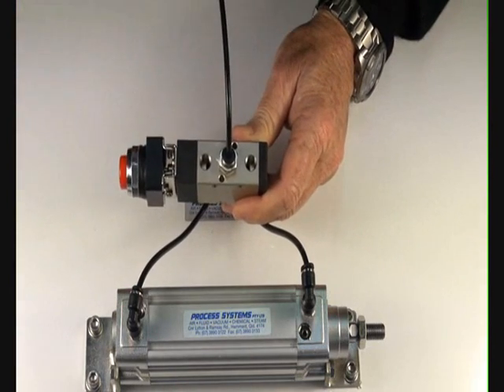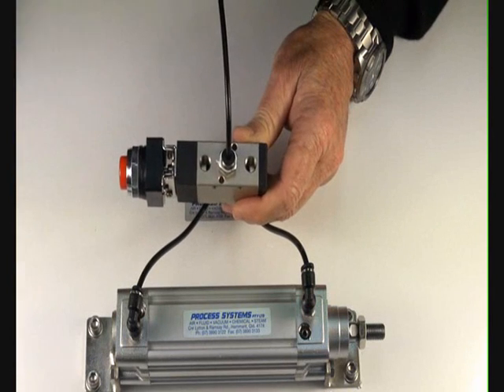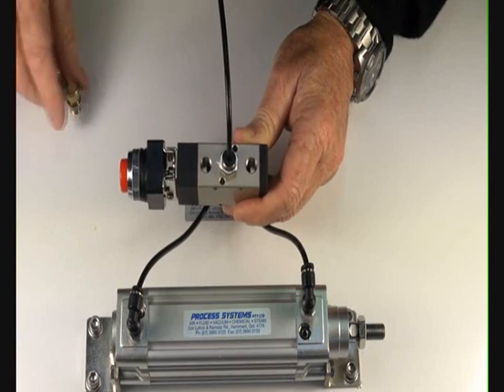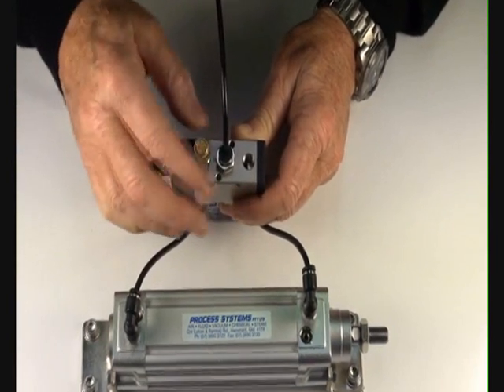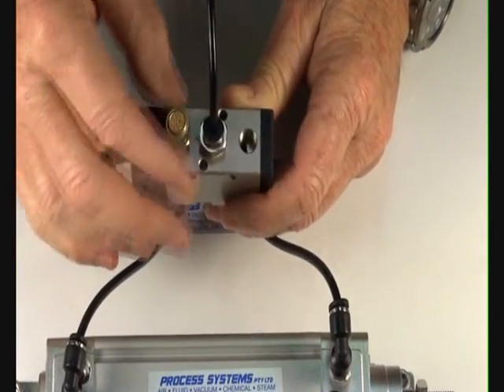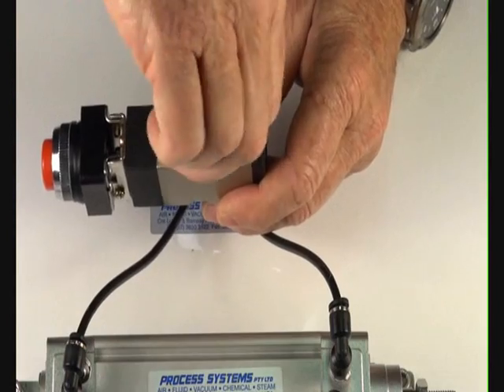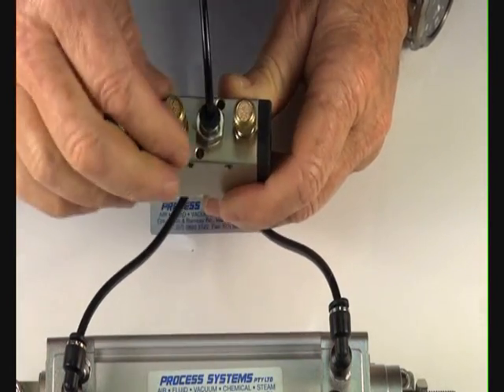For two exhaust ports, we can either put silencers in both ports to reduce the noise down and also stop dust getting inside the valve, or we can use silencer flow control regulators. These will allow us to control the speed of the ram as well as silence the air and keep it clean.